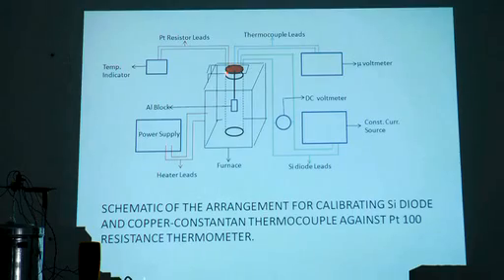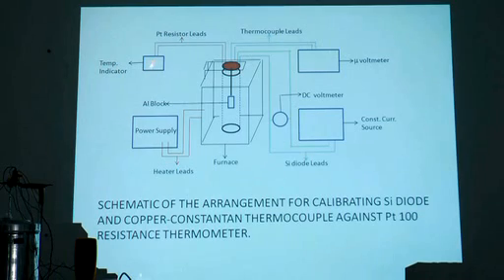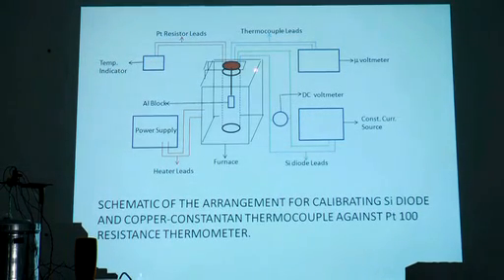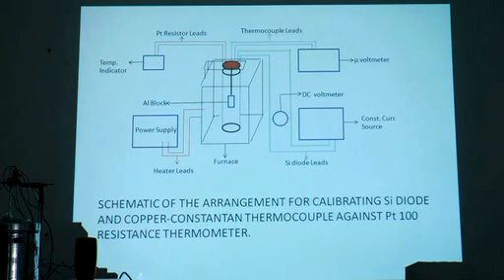There are two terminals which are connected to the platinum thermometer on the aluminum block. They are connected to the temperature indicator. There are two terminals which are connected to the silicon diode. They are connected to the constant current source, and you set a current of 2 milliamperes. There is an RCA plug that is connected to channel 1 of the microvoltmeter. The voltage across the silicon diode is read on this multimeter set at 2000 millivolts.